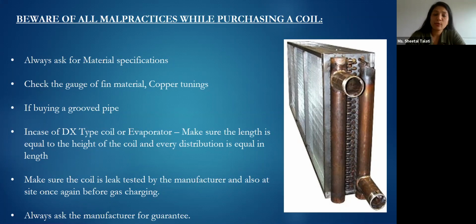So in DX type coils, when you buy a DX type coil, make sure the length of the capillary is the same as the height of the cooling coil. Many people do cheat by reducing the size of the capillary, and the end customers won't even come to know. So that's where the check needs to be done. Make sure the leak testing is done properly so that there is no hassle on site. Before gas charging, we recommend the customer flush the coil once again with nitrogen, and thoroughly test the coil for a few hours on site and keep the nitrogen held at 200 to 250 psi, or check it with a soap solution.